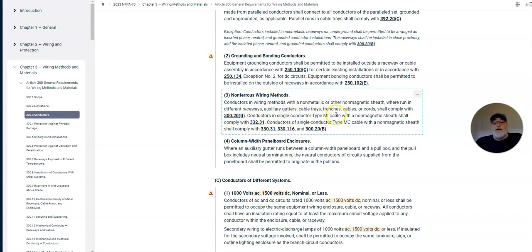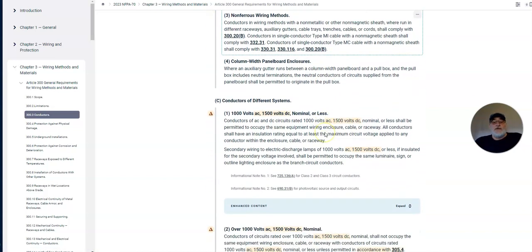Conductors in single conductor Type MI cable with nonmagnetic sheaths shall comply with 332.31. Conductors of a single conductor Type MC with a nonmagnetic sheath shall comply with 330.31, 330.116, and 300.20(B). We could go way deep into this, and we'll get into this later. In the end, every one of these is going to reference back to another point. As long as you remember that you've got to bounce in this book back and forth, back and forth, you'll be able to use this book to find the answers you're looking for. Okay, we're going to go on down through here a little bit further.